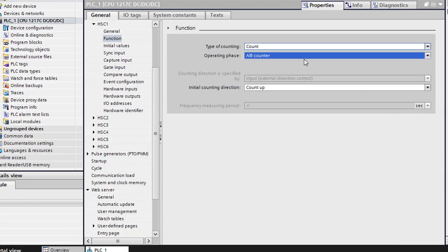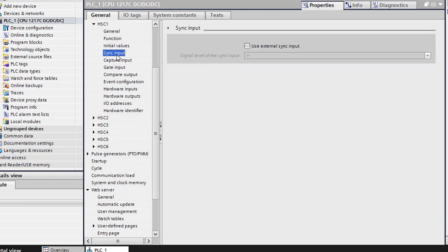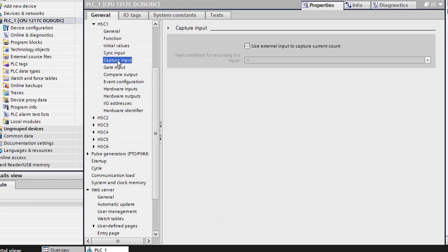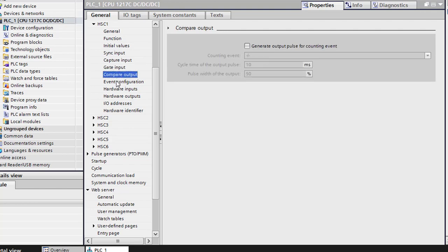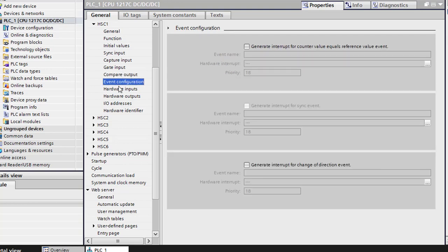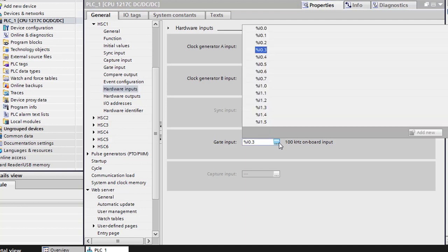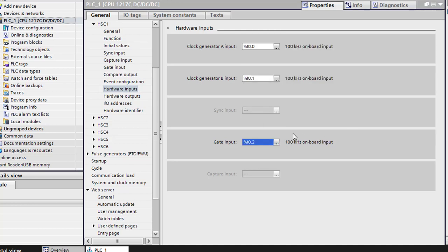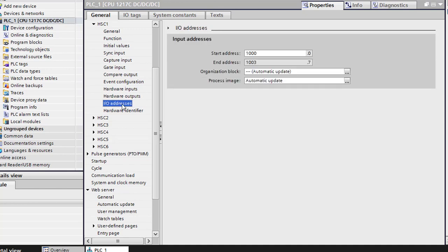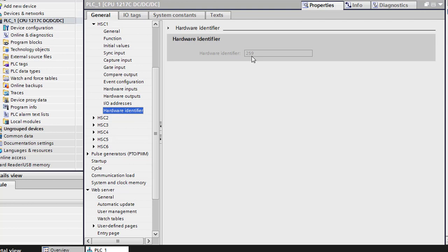So we'll go ahead and minimize this and come back to our project view. So the initial counting direction is up. It doesn't matter which way you put this; it's still going to count in the direction that you wired it. So our initial values are zero. Here's your high limit and low limit. Sync input we're not using. We're not going to use capture, but we are going to use the gate. So we're going to look at the next compare output. We don't use event configuration. We are using hardware inputs. This is where it's important. So we're using input I0.0, I0.1, and I0.2. We're going to change this to 2.